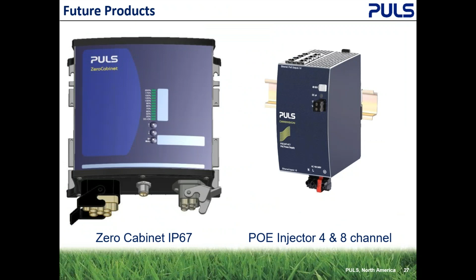Zero Cabinet is our IP67. It's unlike anybody else's IP67 in that it will not be potted. If we looked at the injector to the right and pretended that was a power supply - which there is a power supply in there, with top screens and bottom screens the same way - if we would fill that with an epoxy material, that power supply, which is a 20 amp, would have a maximum output of about 2.5 amps, because the potting material would not allow the heat to escape. So the unit on the left, the Zero Cabinet, is not potted.